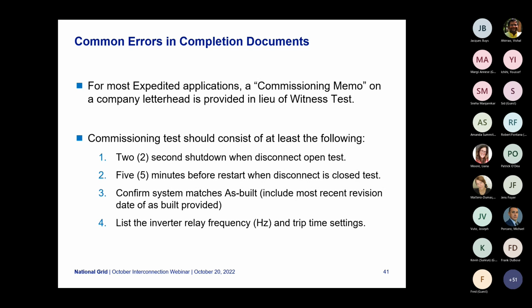And then some errors that we see quite common in completion document submission. For most expedited applications, a commissioning memo on a company letterhead must be provided in lieu of the witness test. And the commissioning test should consist of at least the following: the 2-second shutdown when the disconnect open test, 5-minute before restart when disconnect is closed test, confirm the system matches the as-built, and list the inverter relay frequency and trip time settings. Next slide.